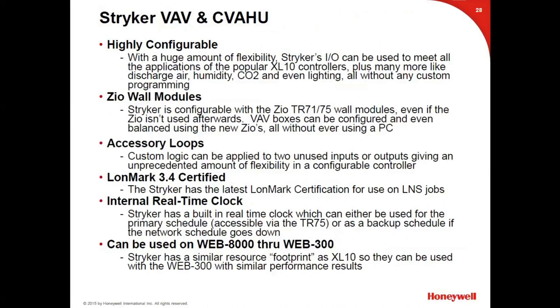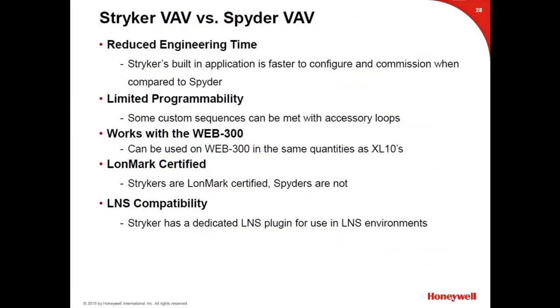The Stryker has a real-time clock, so it doesn't necessarily need to be tied into a building automation system — it can be standalone. It's compatible from the Web 8000 all the way back to the Web 300. Stryker VAV versus Spyder VAV: the Stryker is a bit quicker to configure and download, but you are limited in programmability. It also has LonMark-certified LNS compatibility. The Stryker controller I/O chart is similar to the Spyder charts shown earlier, with the same part-numbering logic.